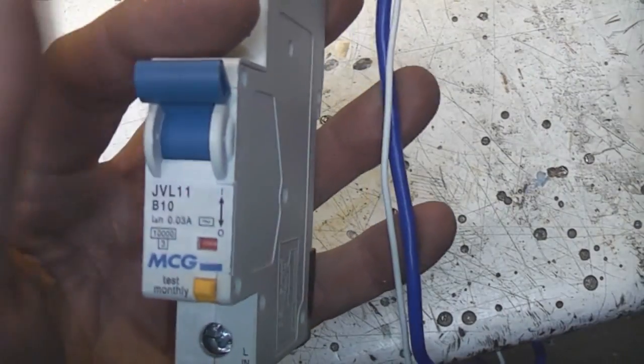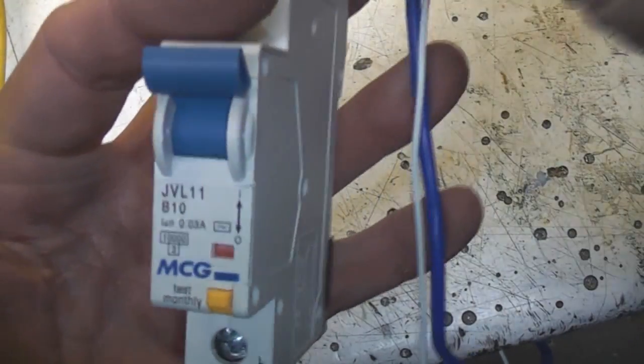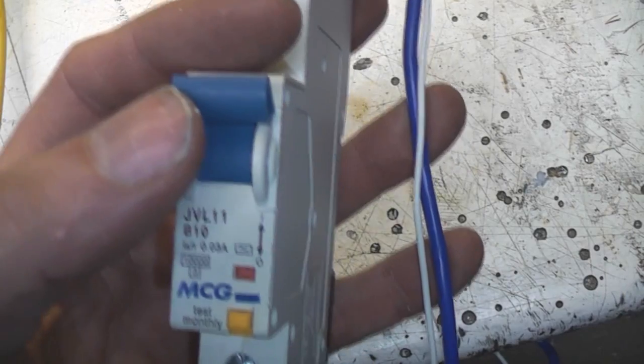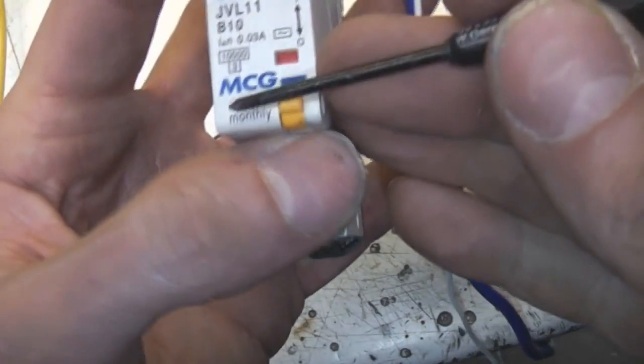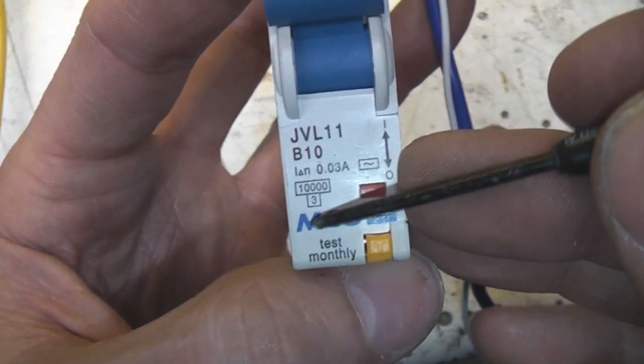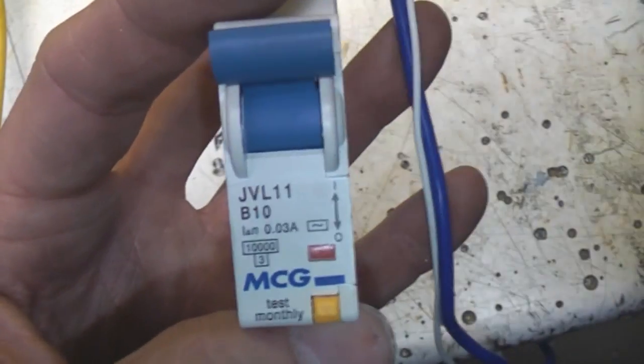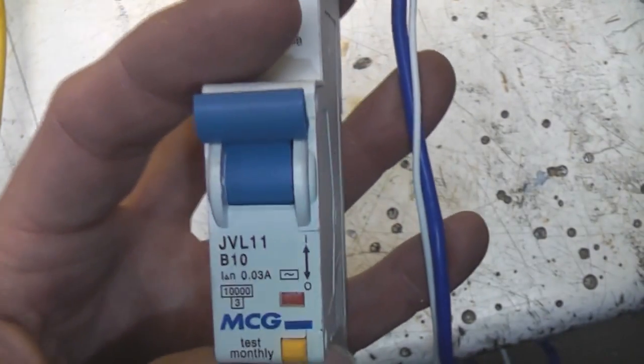So even if our power supply is normally only around 6 amps, if you uprated this to a 20 amp breaker, you then have to uprate all that wiring, which would be a real pain, particularly for a long cable run. So what you do instead is you use a C or even a D breaker so that it withstands that surge, because a surge current for a short period of time isn't a problem.